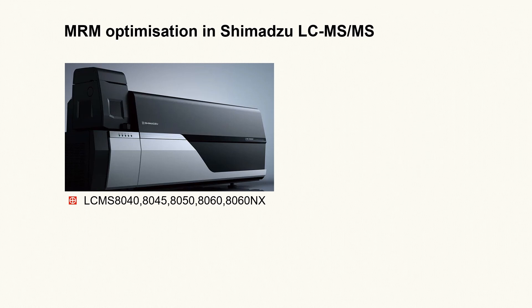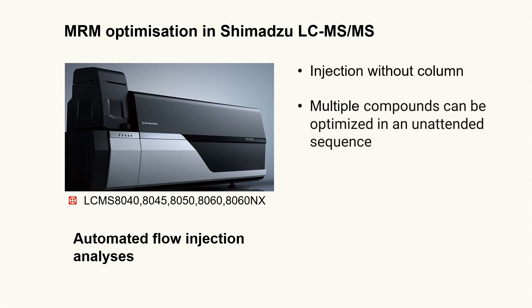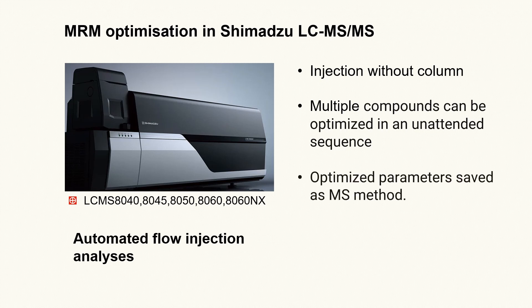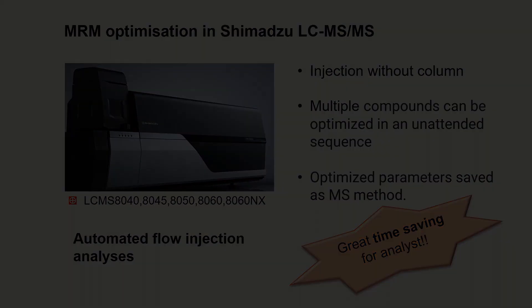MRM optimization can be time-consuming, especially when setting up a multi-analyte analysis method. MRM optimization in Shimadzu LC-MS systems is based on a rapid series of automated flow injection analyses, requiring only minutes to perform. Multiple compounds can be optimized in an unattended sequence, and the optimized parameters will be saved as an MS method, freeing the analyst from tedious work.